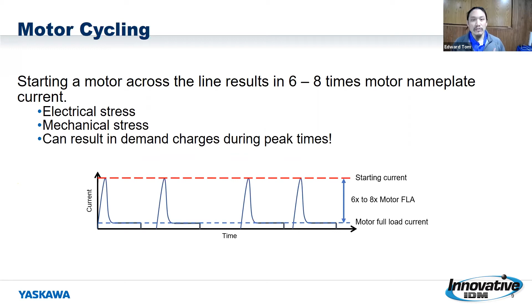Now, the last bullet point I have on here is that depending on when this happens, and depending on the power company, you may get a demand charge. You may have a 10 horsepower motor that you start and stop, no problem. But imagine getting into larger and larger motors, say 300 horsepower, 500 horsepower. During peak times, if you start it up at just the right time, or multiple motors start up at that time, you're going to get a surge of current, and the power company is going to look at it and say, you've asked enough demand, we're going to charge you for going over a certain amount. So that's something to really watch out for when it comes to cycling that motor on and off and using it as a means to control it.